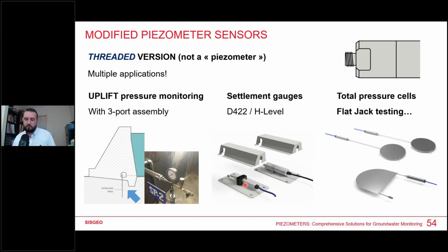Also, we have this system that many of you, I think, know. So these are the settlement gauges. We can install multiple sensors like this, and each sensor is connected to a T-shaped connector, and all the sensors are linked together with water lines. When a sensor is rising, its pressure is lowering, and when the sensor has settlement, the pressure is rising. So with the pressure, we can monitor the settlements. And on the right, you can see another type of use of these sensors with threads, connected with a pressure pad. This pad is filled with oil, and this oil is connected to this sensor. So when a pressure is applied on this pad, the pressure raises. It's quite simple, the principle, but you can use it for many diverse applications.